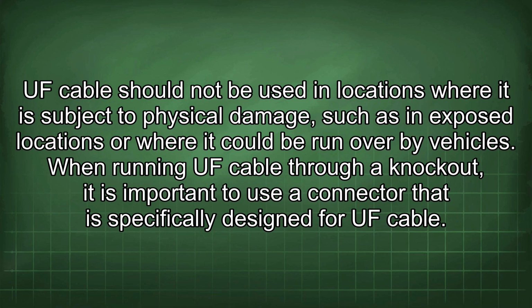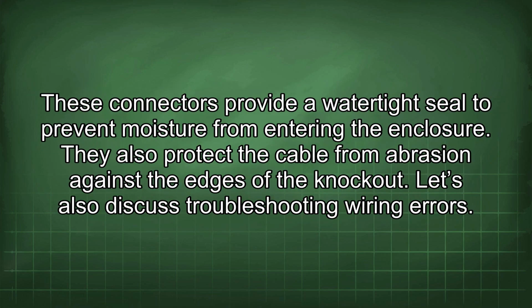When running a UF cable through a knockout, it is important to use a connector that is specifically designed for a UF cable. These connectors provide a watertight seal to prevent moisture from entering the enclosure. They also protect the cable from abrasion against the edges of the knockout.